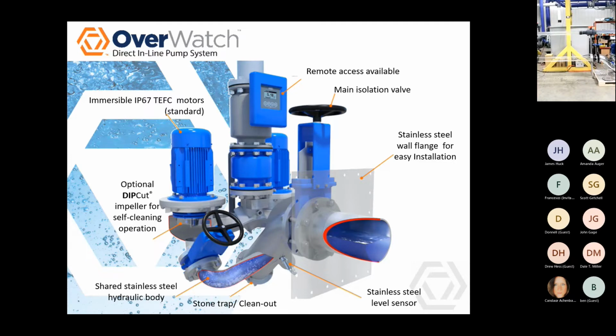The motors are IP67 TEFC cooled motors. This is the key difference between us and submersibles, besides all the other things I mentioned, right? Submersibles are defined by the number of starts and stops because they use the pump liquid to keep them cool. We don't. We use ambient air to keep us cool. So we are not defined by the number of starts and stops. We're going to use that ambient air to keep us cool and the fan on top of the motor to keep us cool. They are immersible IP67 motors, so they do have the ability to become submerged and still operate.